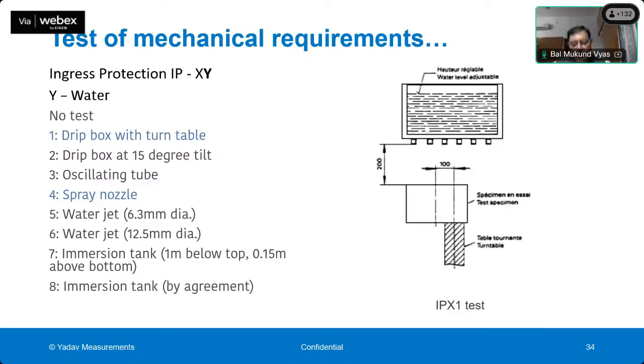If it is an outside meter, an outdoor meter, then the meter is subjected to the 4th level of the test, which is the spray nozzle. In this kind of test, the meter is subjected to a spray of water with the meter rotated in different directions, from the top side, the front side and the back side. The meter is sprayed with water as per the specified standard, and then subjected to the insulation test and opened to see if there is any ingress of water.